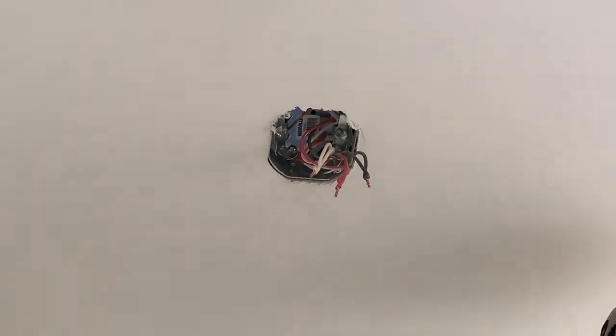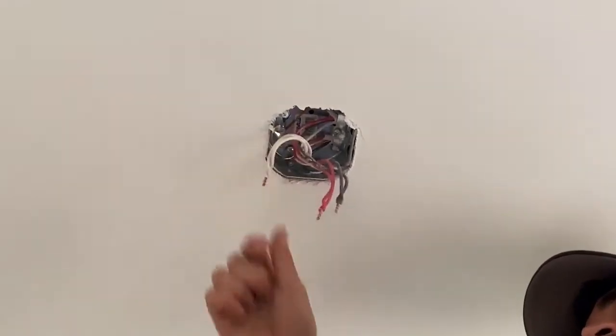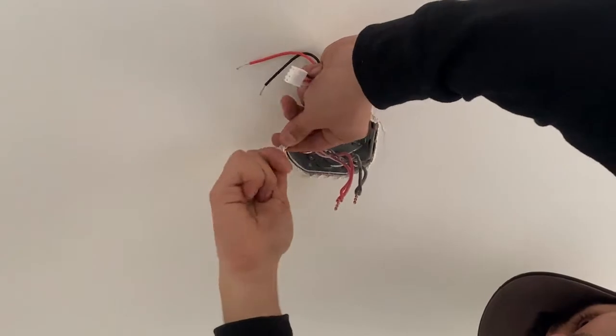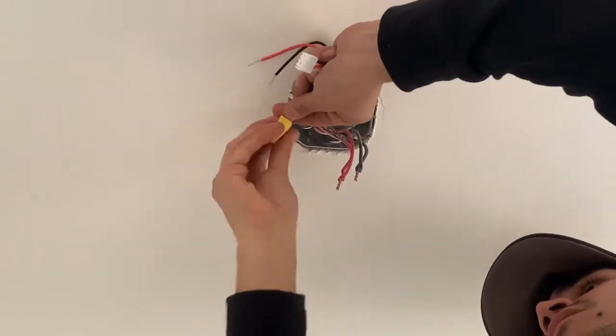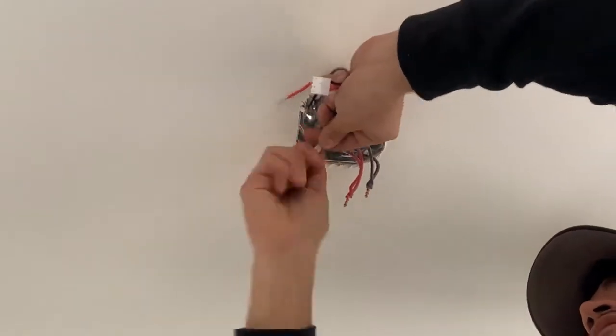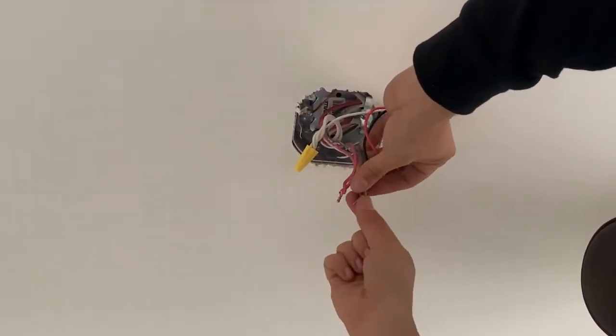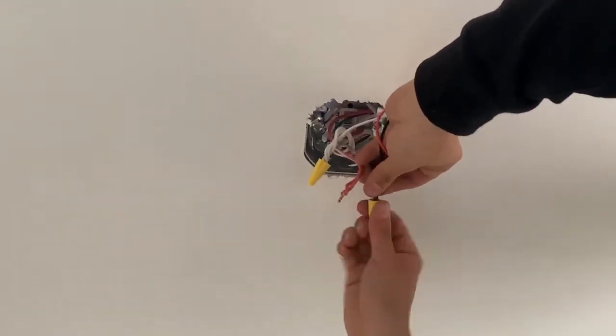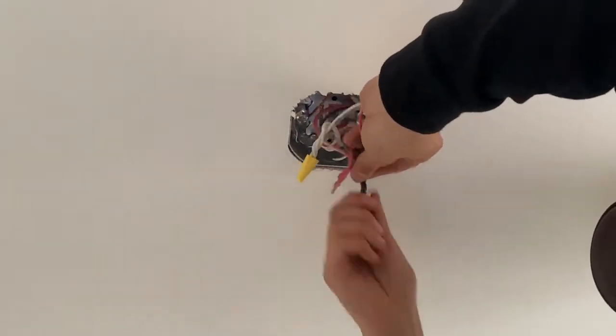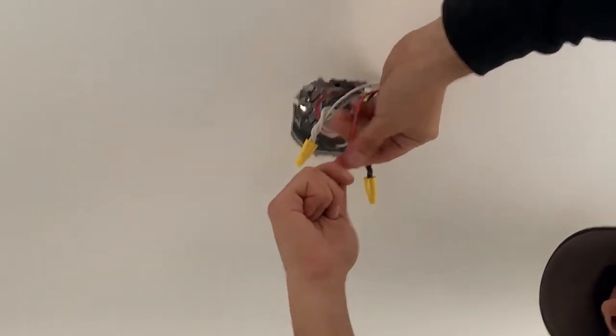My journeyman is now going to demonstrate putting the actual whip for the smoke detector onto the connections. First he's going to do is white, and then he's going to do his black. He's twisting his wire nuts on clockwise, because that's important, and then he's going to do his red interconnect.